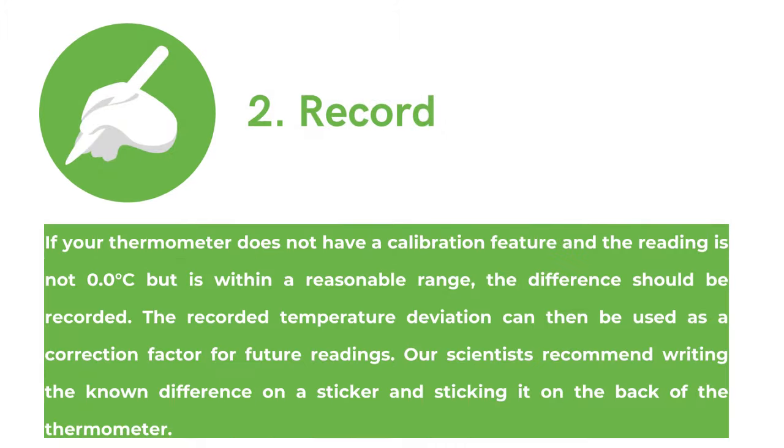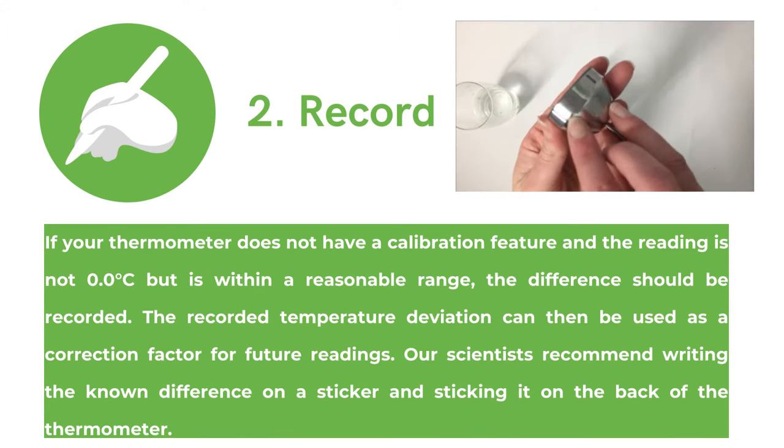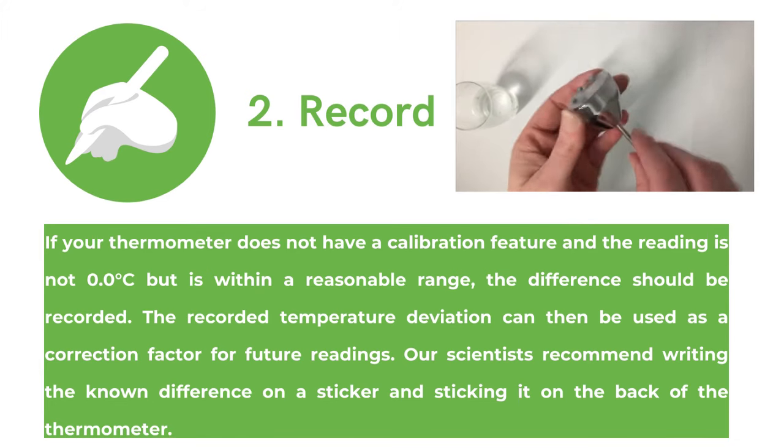The second is record. If your thermometer does not have a calibration feature and the reading is not zero but is within a reasonable range, the difference should be recorded. The recorded temperature deviation can then be used as a correction factor for future readings. Our scientists recommend writing down the known difference on a sticker and sticking it to the back of your thermometer.